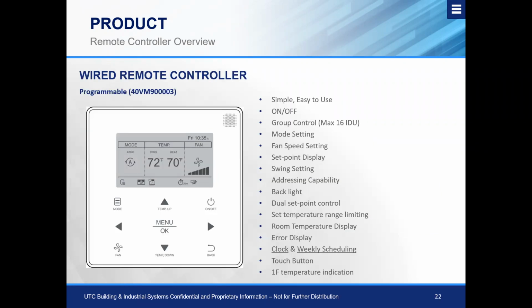With our programmable wired controller, just like any other local control in the VRF system, this has your temperature adjustments, temperature changes, and load changes. But this also has the ability, of course, to schedule and to show technical data such as temperatures and whether the unit is currently running, and you can do some addressing from here. So it's much more than just a wall thermostat, which is why it's called a programmable wired controller.